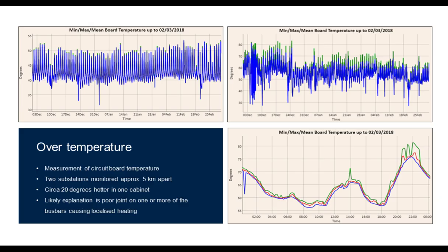The red is the minimum, and the key one here is the green, which is the maximum temperature. As you'll see here, we've hit just over 80 degrees C, but at 10 o'clock at night. Clearly at 10pm there's no solar gain related to this, so it has to be from energy within the substation. In this instance, we believe it's from a loose connection in the LV panel that, when under significant load at night, overheats and results in a fire.